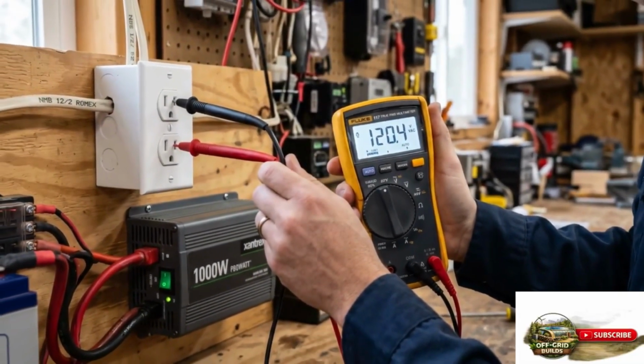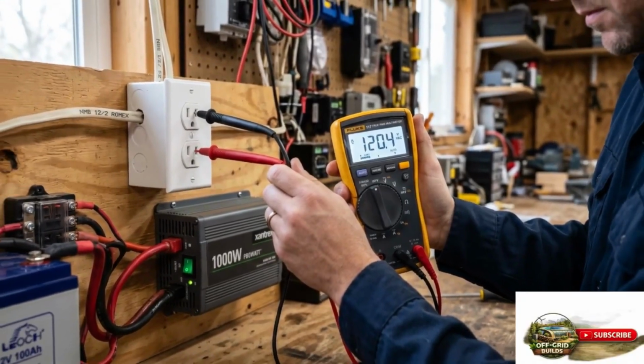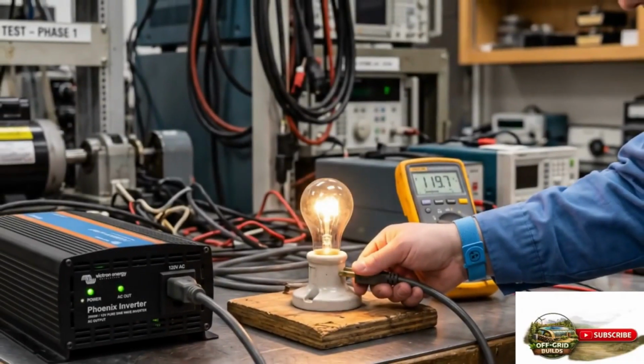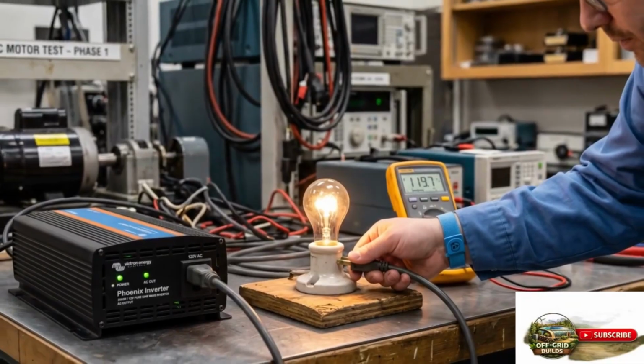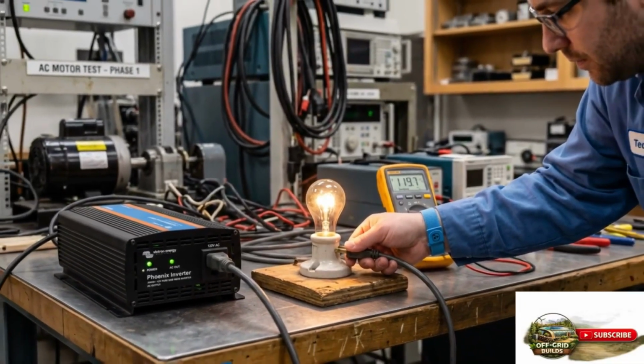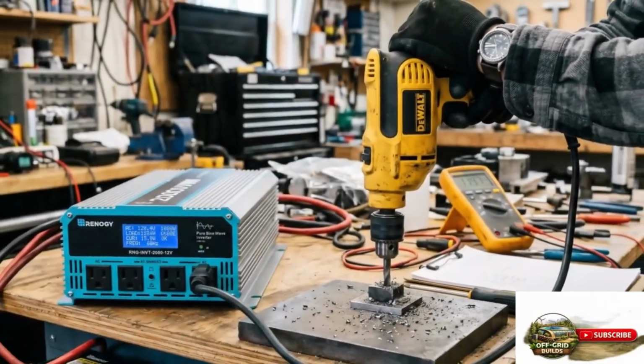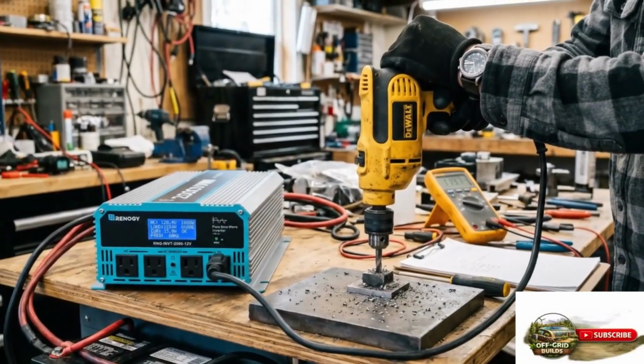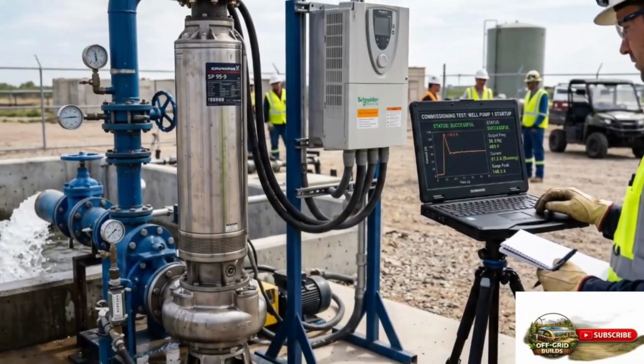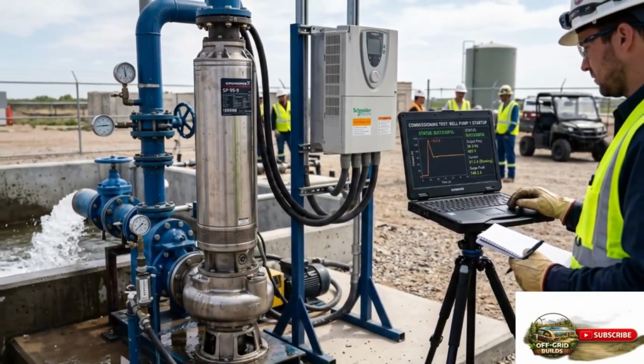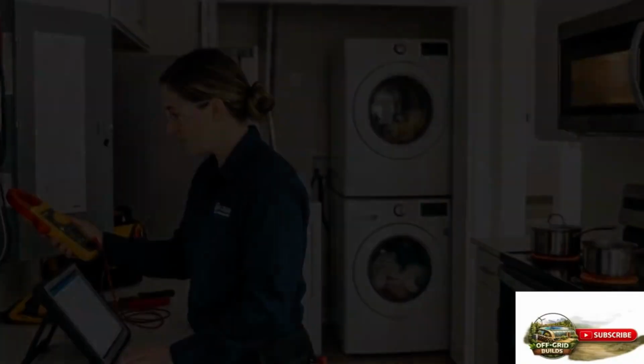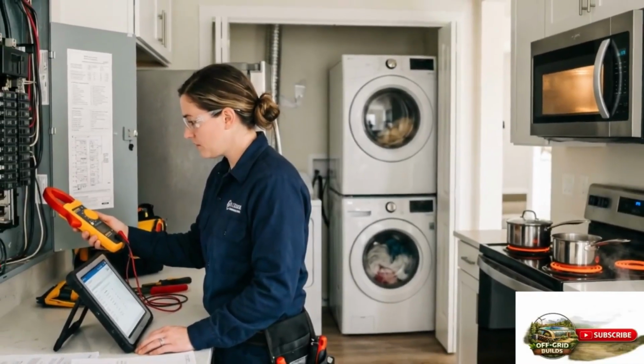After verifying charge controller operation, connect the inverter and verify that it powers on correctly and produces AC output at the expected voltage and frequency. Test AC loads progressively, starting with small resistive loads and progressing to motor loads, verifying that the inverter handles each load correctly. The most common installation mistake in large off-grid systems.